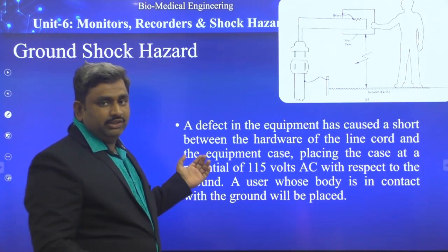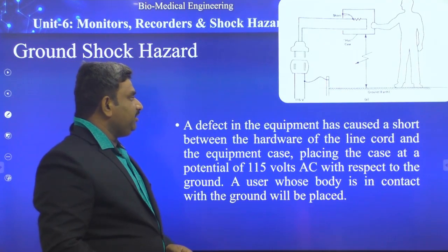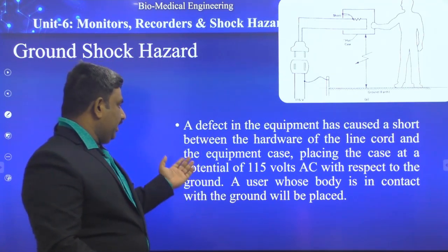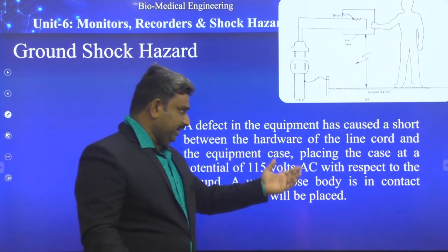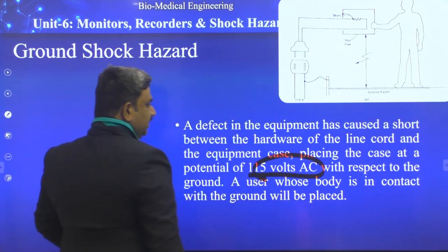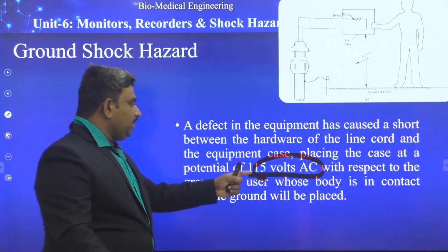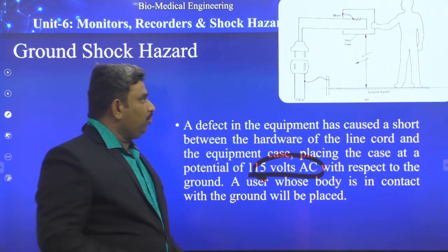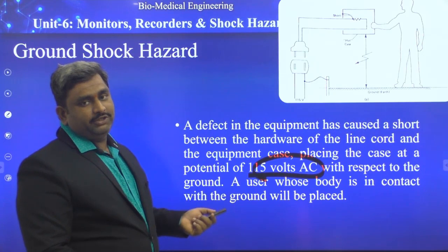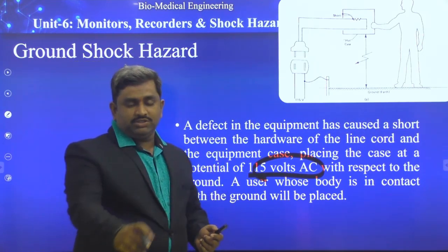A defect in the equipment has caused a short between the hardware of the line cord and the equipment case, placing the case at a potential of 115 volts AC with respect to ground. A user whose body is in contact with the ground will be placed in this circuit. Whichever patient is connected to the ground, that patient's body will get electrical shock from this situation.